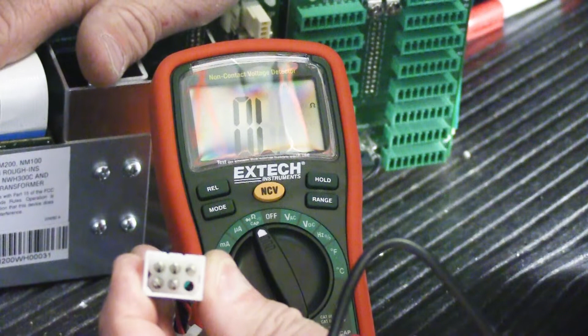If everything in the master station is good and there are no shorts, there should be no continuity between the appropriate pins, 1 and 2, 3 and 5. If there's no short in the master station, if everything here is good and there's no damage, there would be no continuity between 1 and 2, and then 3 and 5.